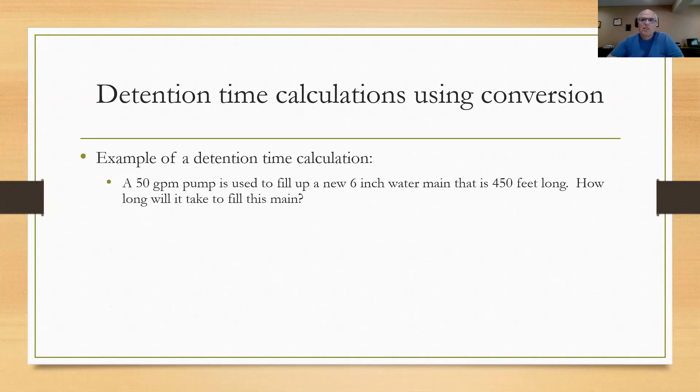Here's another detention time calculation using a conversion. Example where they're telling you that you have a 50 gallon per minute pump. You're out in the field and you're using it to fill up a new 6-inch water main. It's 450 feet long. How long is it going to take to fill that main? Well, here they haven't given you a volume. You've got to calculate the volume on your own first, so that you can do the detention time calculation. So the way I set this up was I set my formula of volume divided by the flow rate for detention time. I calculate the volume of the pipe.